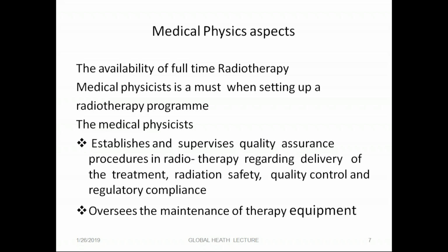guidelines. The medical physicist also oversees the maintenance of therapy equipment. And it's important to have preventive maintenance rather than to wait until the machines are broken down and require repair, because that will affect the treatment of patients.